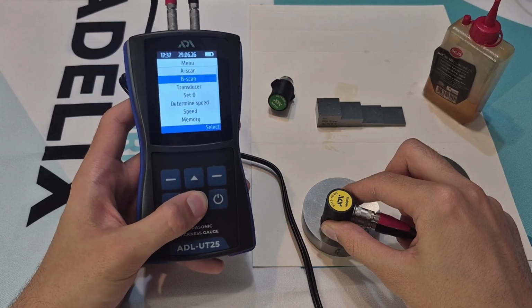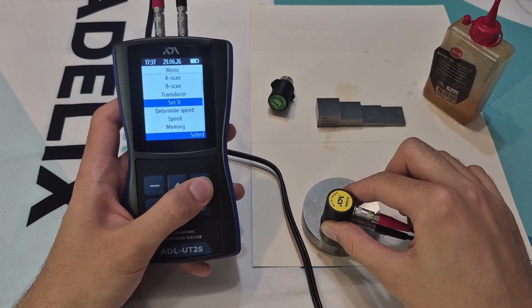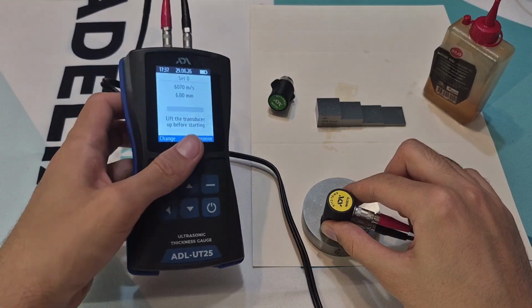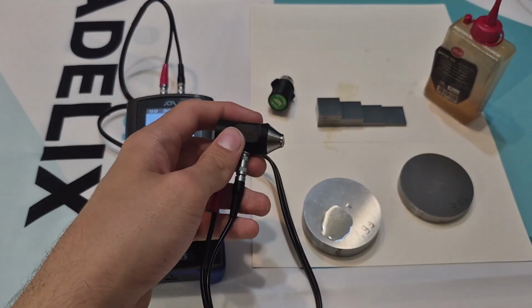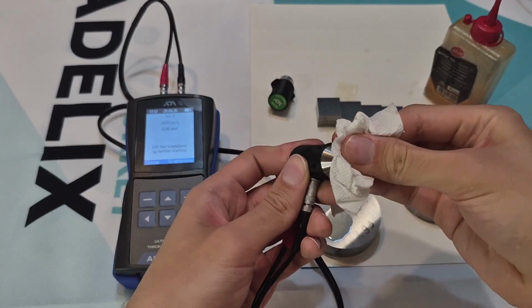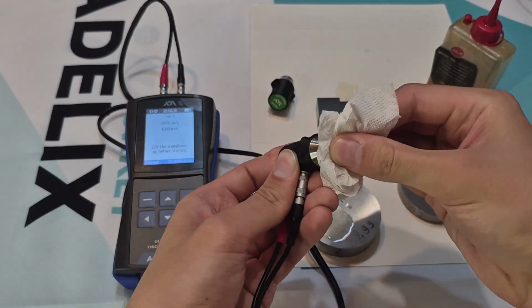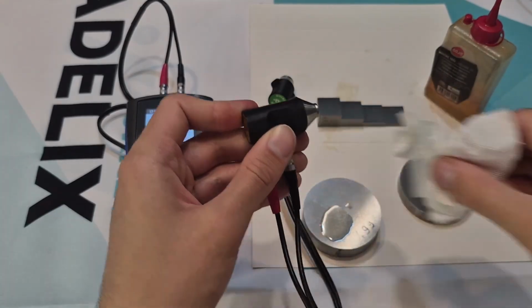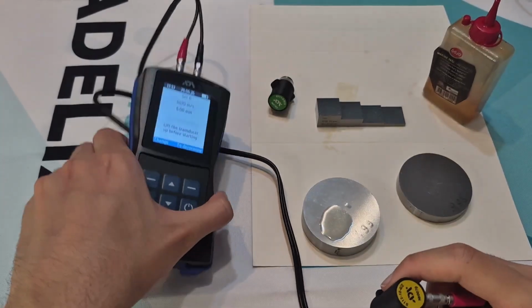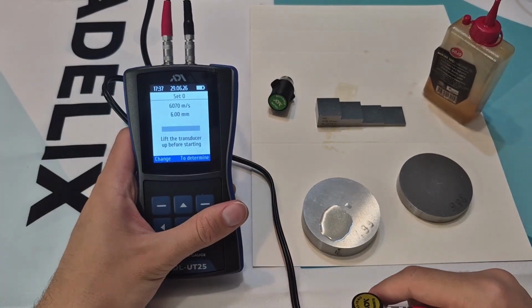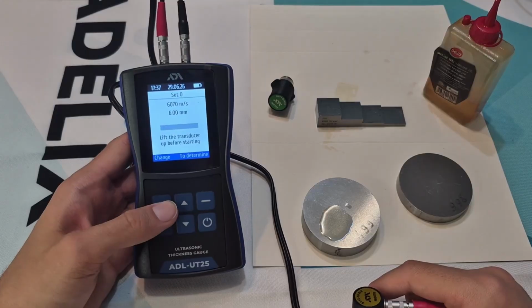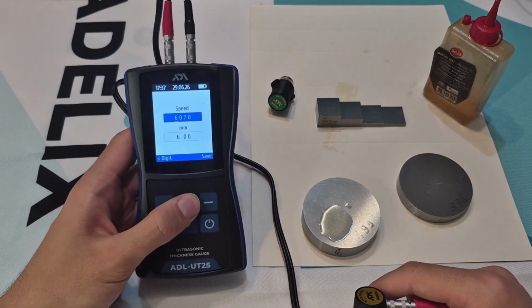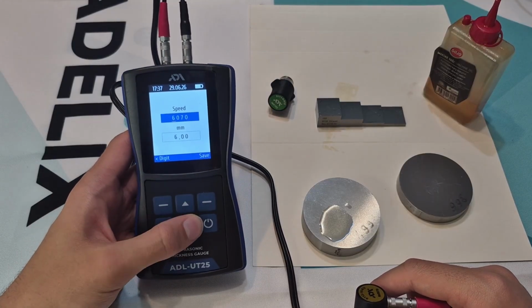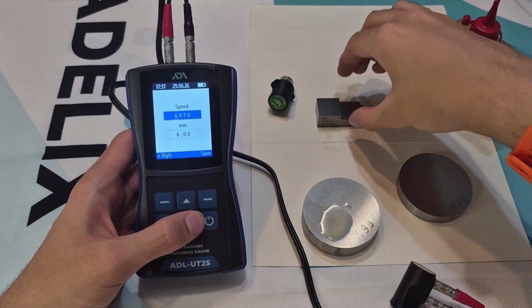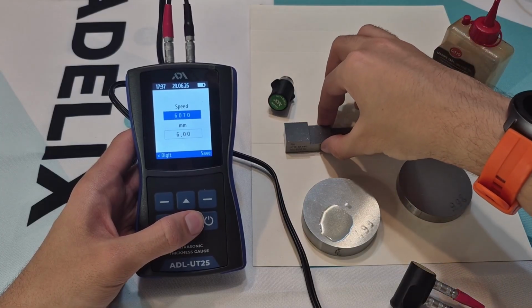Before starting measurements, the transducer must be calibrated. To do this, we open the Set 0 section. Before performing zero calibration, the surface of the transducer must be clean and dry. Next, we select the sample that will be used for calibration. We press Change. Here the ultrasonic velocity is set. I will perform zero calibration using a step calibration block with steps of 15, 10, 5 and 3 millimeters.